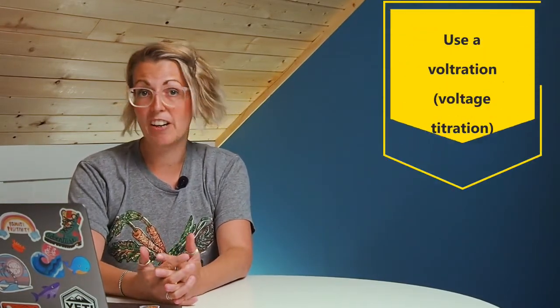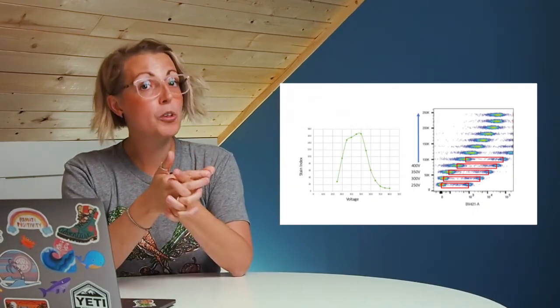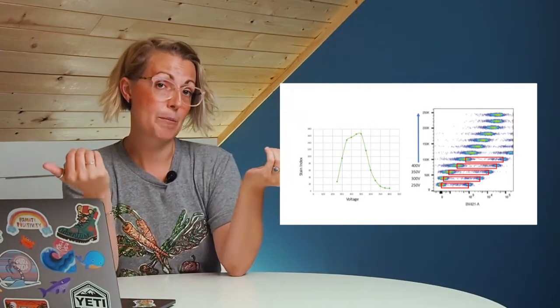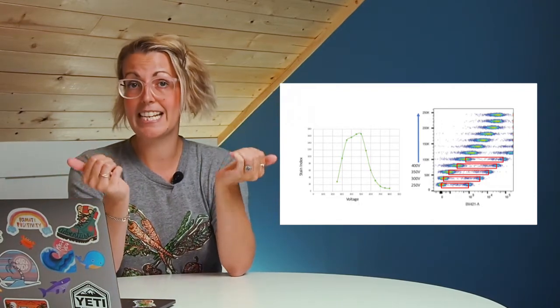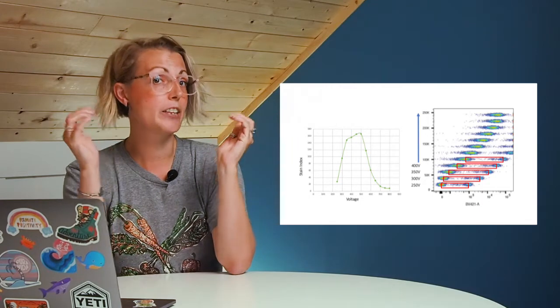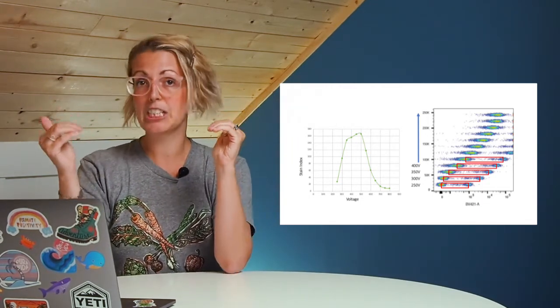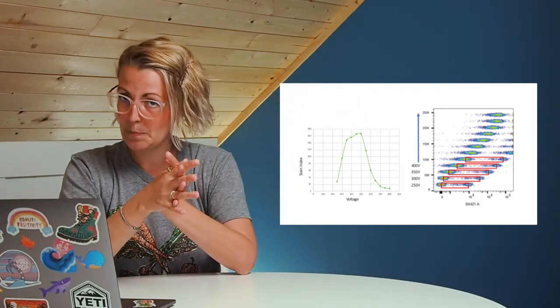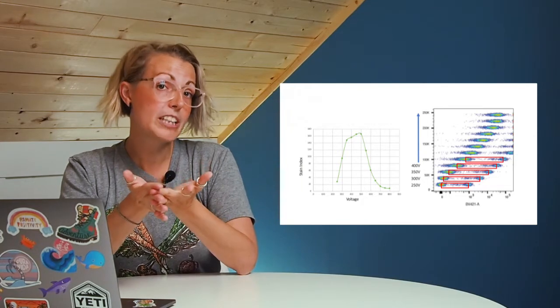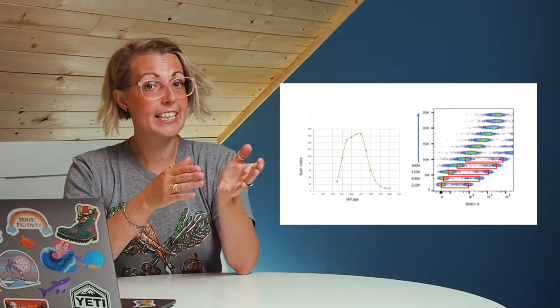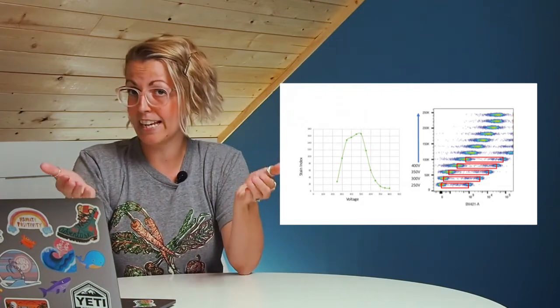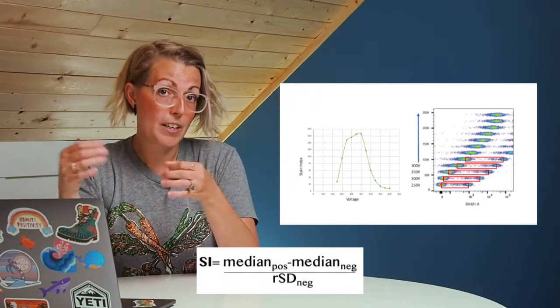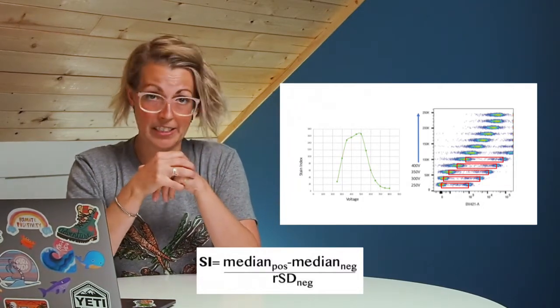Somewhere in the middle, you have the method I usually use, which is a voltration, essentially a voltage titration. The graphs beside me will give a nice representation of how a voltration will work. Looking at the first sample, you can see I've run my sample at 250 volts. I've then taken this exact same sample and run it again at 300 volts, then 350 and so on, increasing the voltage by 50 volts every time. What I'm looking for is the difference between the negative and the positive, factoring in the spread of the negative. This is your stain index.